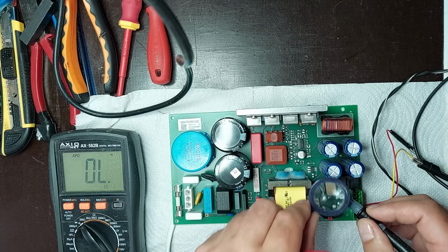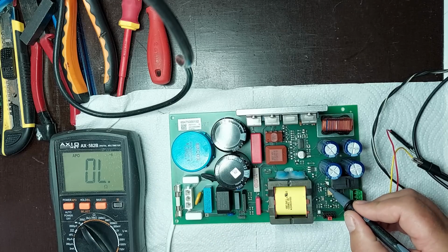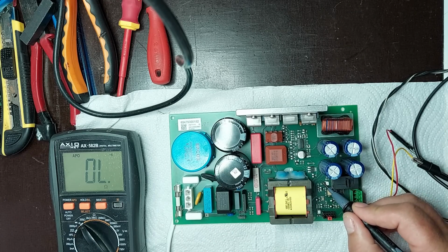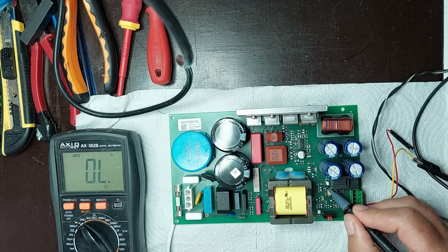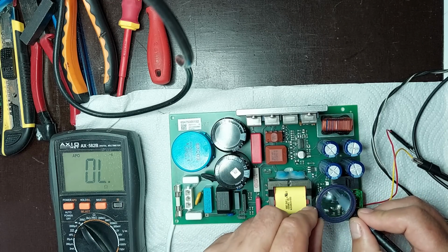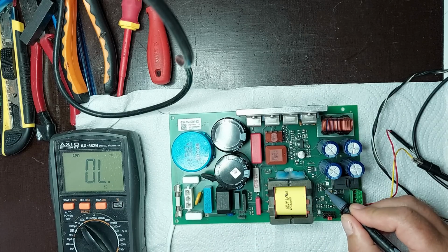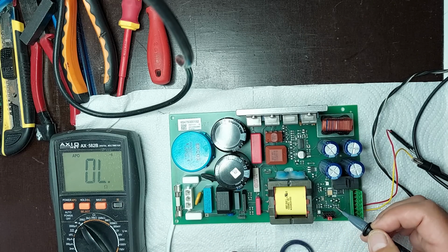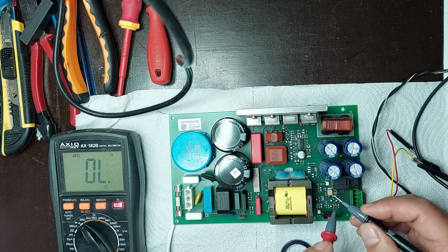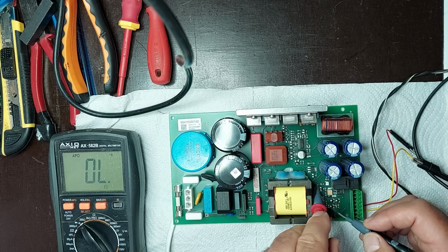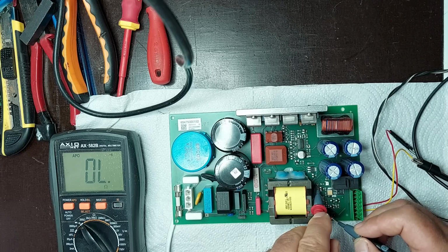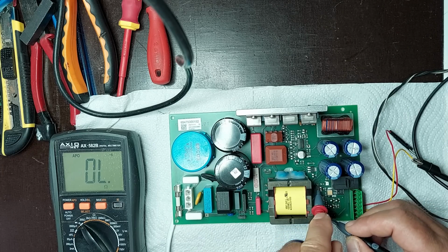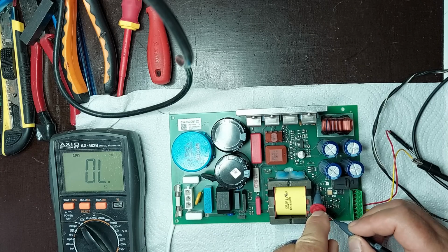It seems that this power supply also includes an on/off control circuit that drives a switching transistor. This transistor is responsible for enabling or disabling the 24V DC output on the connector, based on an external control signal. In other words, the output is electronically switched and not always active, which is an important detail to consider during testing and troubleshooting.